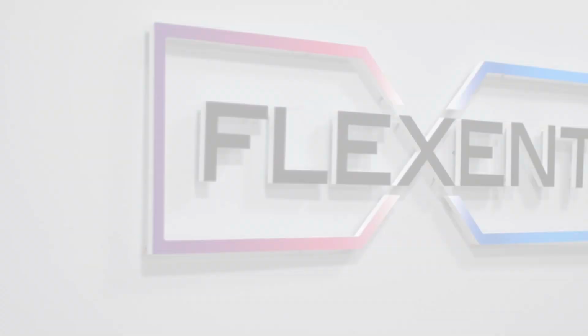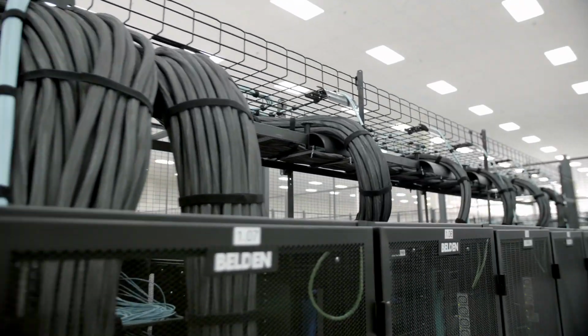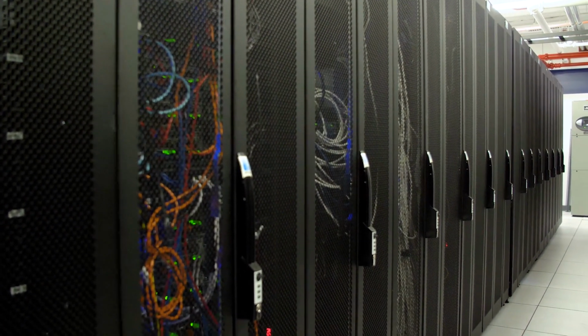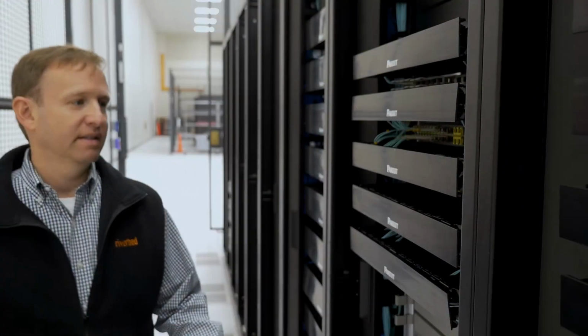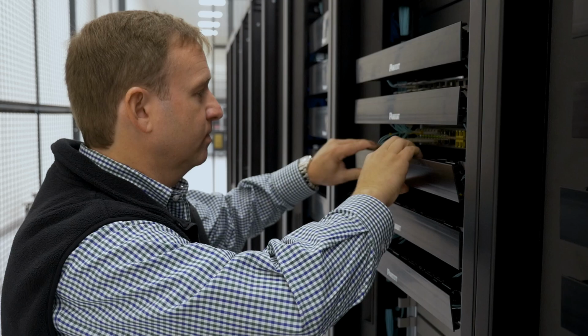our high density capabilities. In our Gen 4 data centers, we can support densities as high as 1,600 to 2,000 watts per square foot, which is really quite unprecedented in the industry. Your traditional data centers can support anywhere from 600 to 700 watts per square foot. You have to be able to power and cool a lot of equipment in a very small amount of space. And to be honest with you, I think that's one of Flexential's biggest secret sauces. We looked all around the country at multiple data centers, and we weren't able to build that much equipment in that small of a space. We would have had to take 2, 3, maybe sometimes 4 times as much rack space to do it somewhere else. So that's really one of the biggest drivers that led us here.